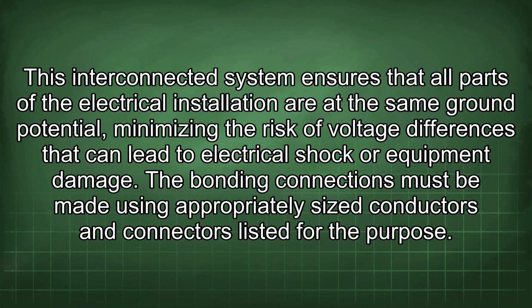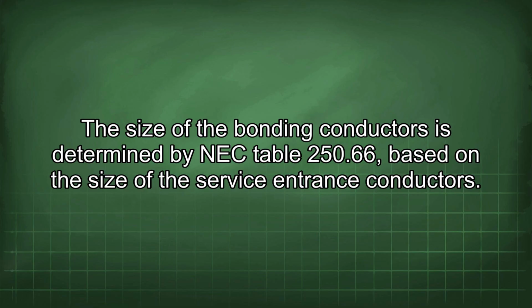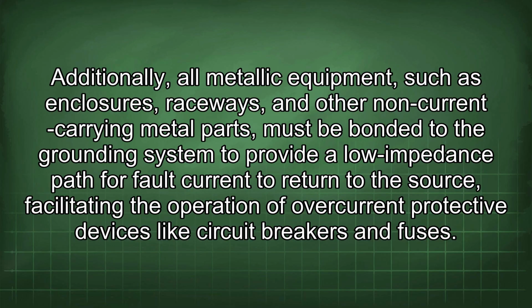The bonding connections must be made using appropriately sized conductors and connectors listed for the purpose. The size of the bonding conductors is determined by NEC Table 250.66 based on the size of the service entrance conductors. Additionally, all metallic equipment, such as enclosures, raceways, and other non-current carrying metal parts, must be bonded to the grounding system to provide a low impedance path for fault current to return to the source, facilitating the operation of overcurrent protective devices like circuit breakers and fuses.